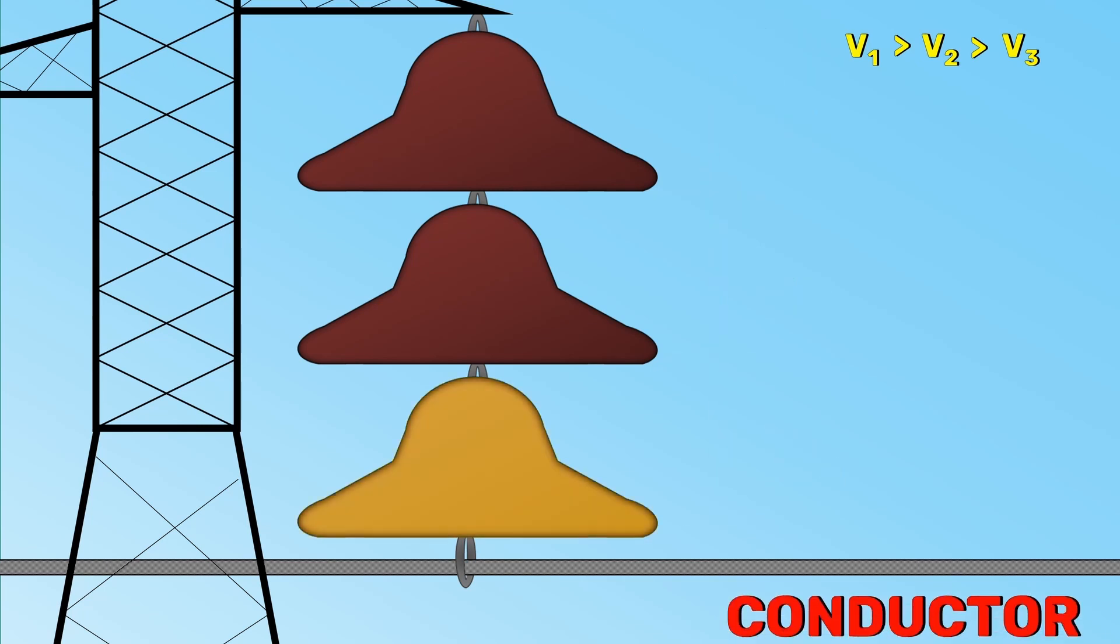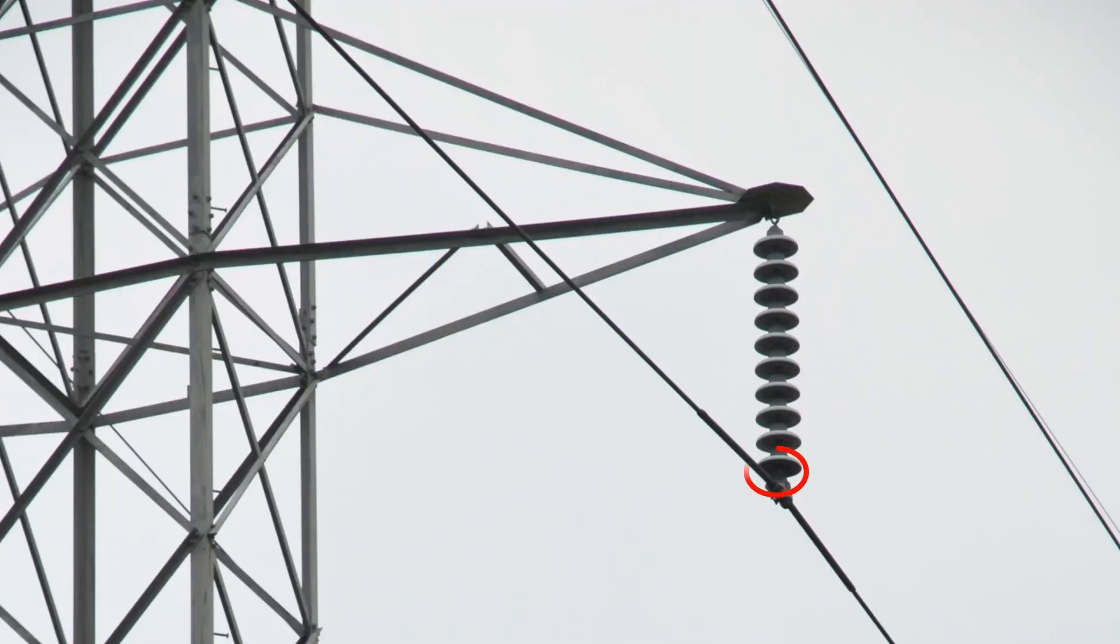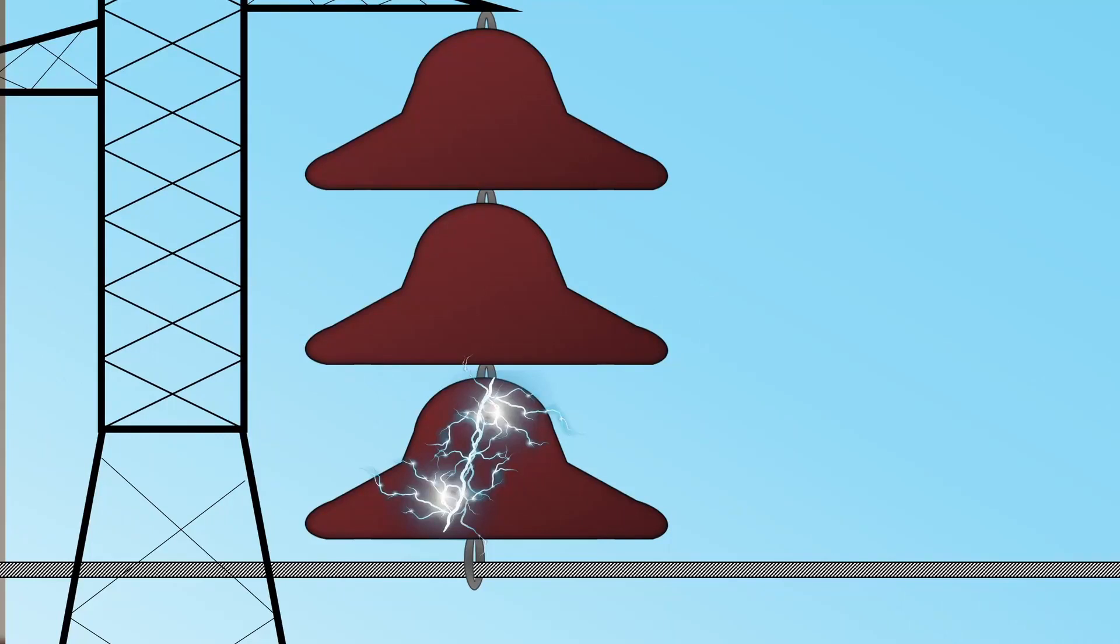The disc nearest to the conductor has the maximum voltage across it. As we move towards the cross arm, the voltage across each disc goes on decreasing. Therefore, the unit nearest to the conductor is under maximum electrical stress and is likely to be punctured.